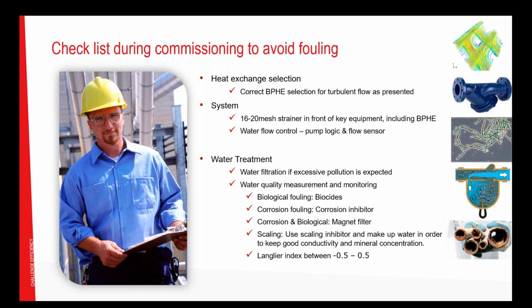The recommendations for installing a brazed plate heat exchanger are very similar, if not identical, to any other heat exchanger. We want the heat exchanger to be correctly selected. We want to have turbulence. We don't want it to be over-dimensioned to any large extent. We want there to be a strainer, not a filter, but a strainer, to avoid large chunks of stone or pebbles getting inside the heat exchanger and blocking it.